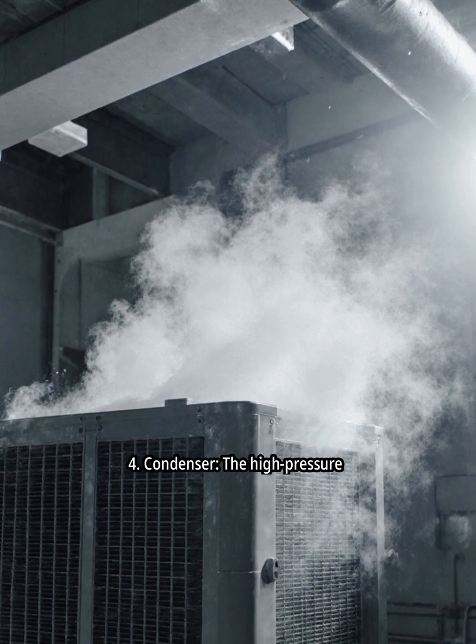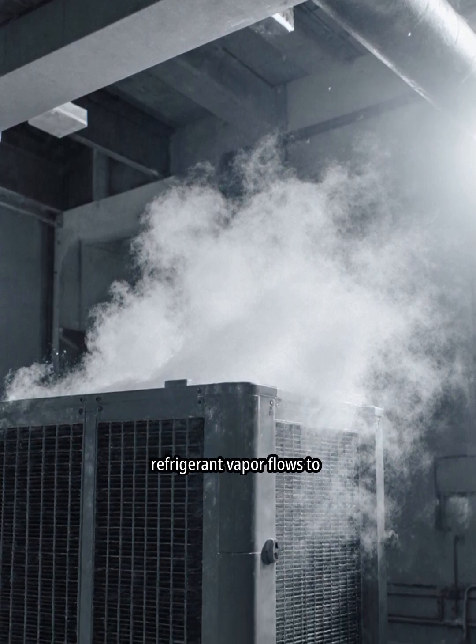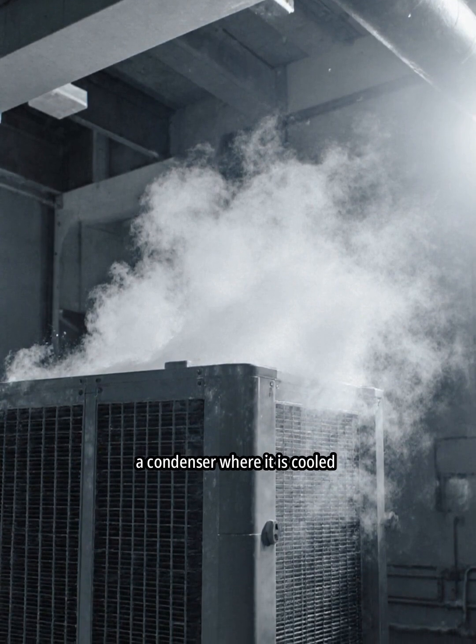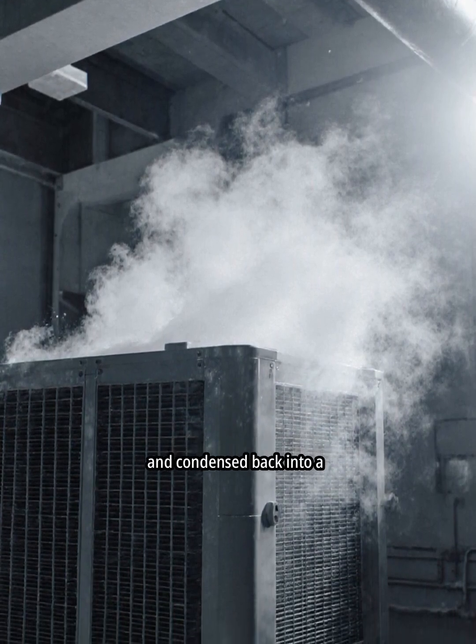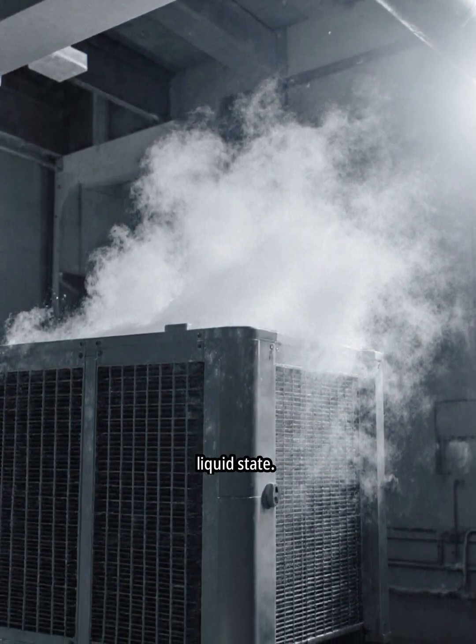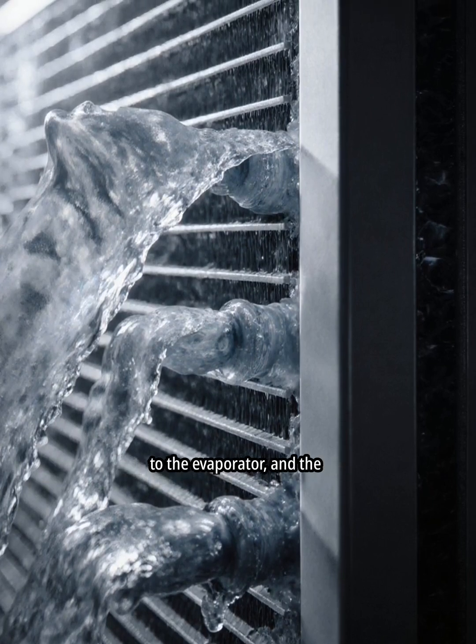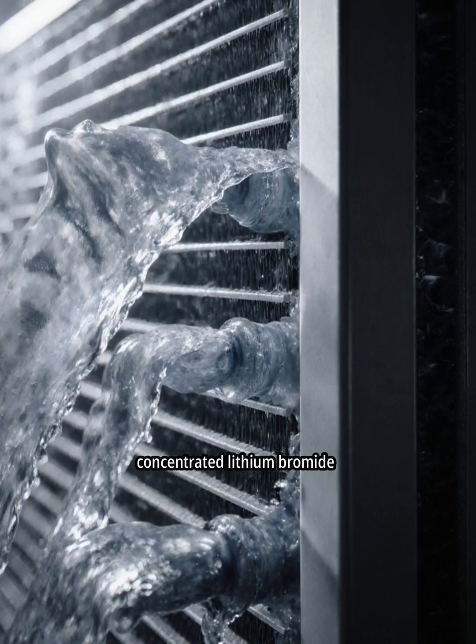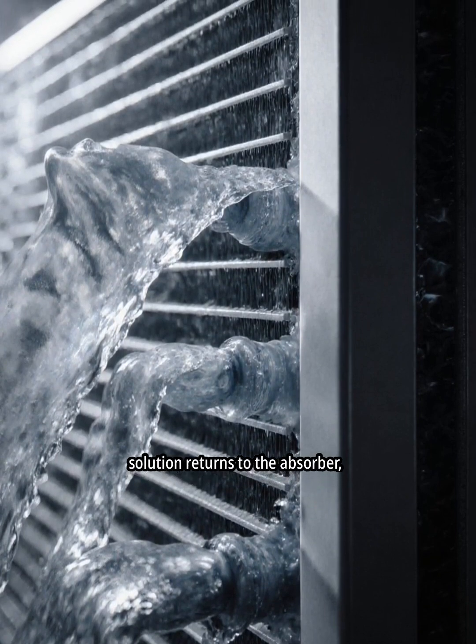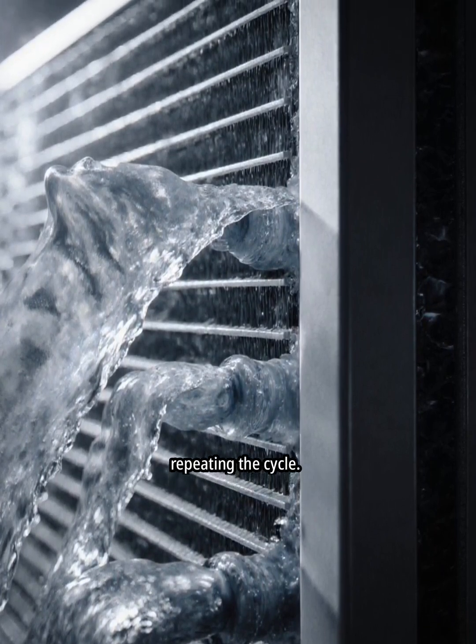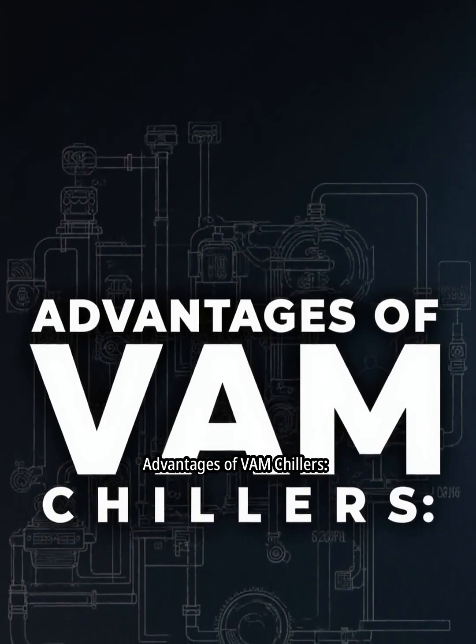4. Condenser. The high-pressure refrigerant vapor flows to a condenser, where it is cooled and condensed back into a liquid state. The condensed water then returns to the evaporator, and the concentrated lithium bromide solution returns to the absorber, repeating the cycle. Advantages of VAM chillers.